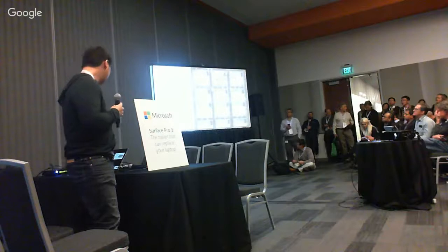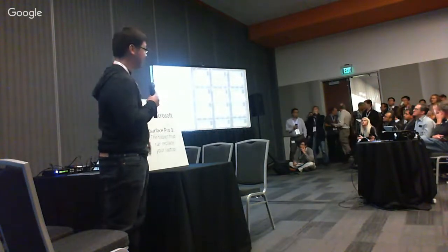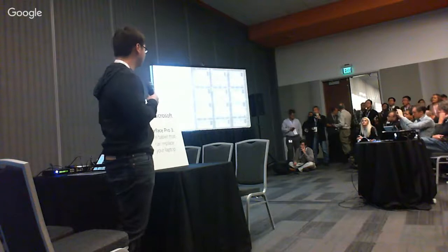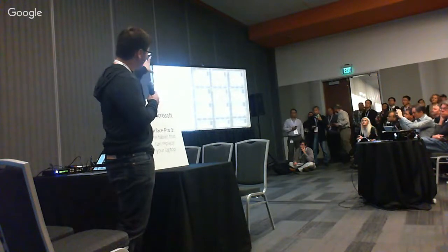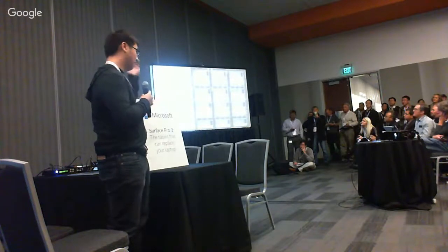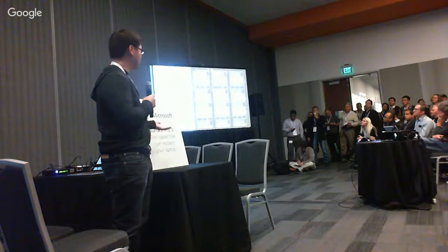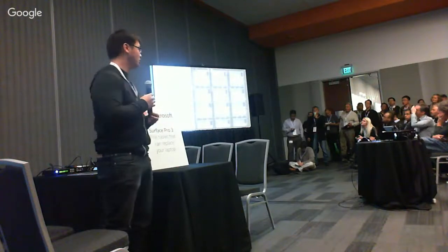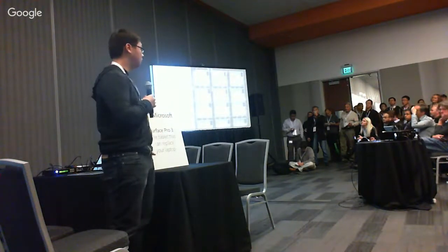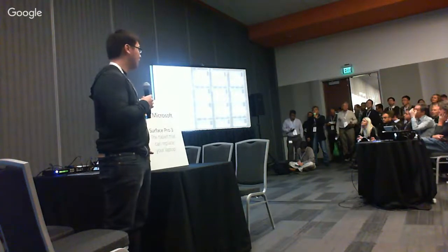Actually, before I go to topology, I'll talk about Open Rack a bit. So this is actually 3 racks put beside each other, so it's kind of confusing that we put 3 racks. But in Facebook, we put 4 Big Surs in 1 rack because of power limitations in our data center. But each server, when we're running our AI applications, is consuming about 2.5 kilowatts. So 1 rack is about 10 kilowatts of power.